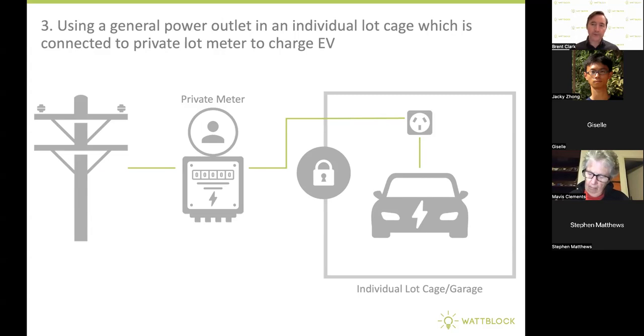This is the problem of the individual owner to manage, so they don't trip their own breaker. But if you had, say, 3 individual apartments all on the same phase on a meter board of 9 apartments, and you happened to have 3 electric vehicles charging on those 3 different lot meters all on the same phase, you might overload that phase on the apartment distribution board. So you'd need to look at load balancing equipment, or timers that stop particular power outlets in cages from charging simultaneously.